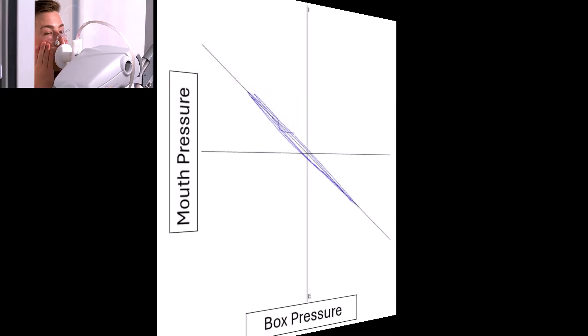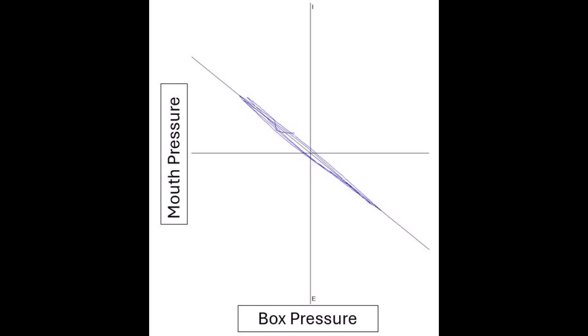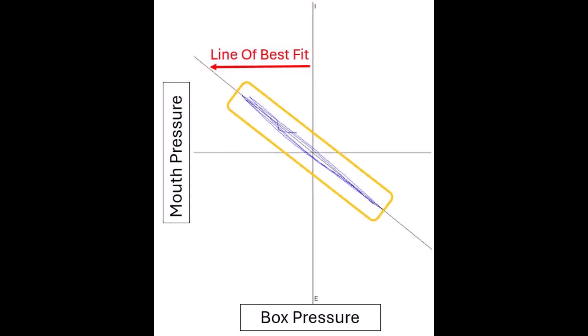When performing lung volume testing, we close the mouth shutter and ask the subject to gently pant. The tracing displayed measures mouth pressure over box pressure. The solid black line that goes through the tracing is called the line of best fit. The computer uses all of the data points from the tracing and places the line of best fit through the average of those data points. In general, the line of best fit should be at the same angle or tangent that the blue tracing is at. If the line of best fit is not at the correct angle, then an adjustment is needed.